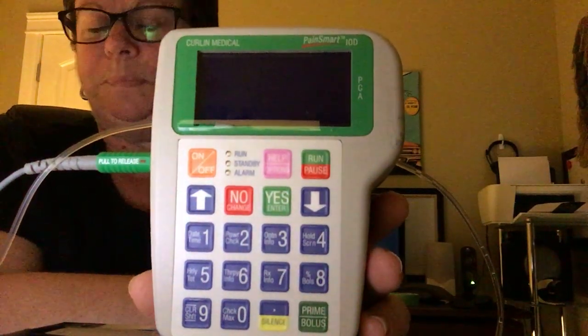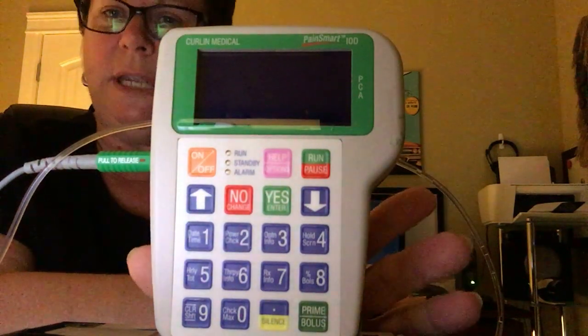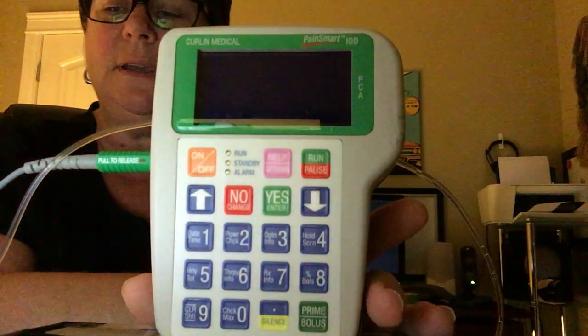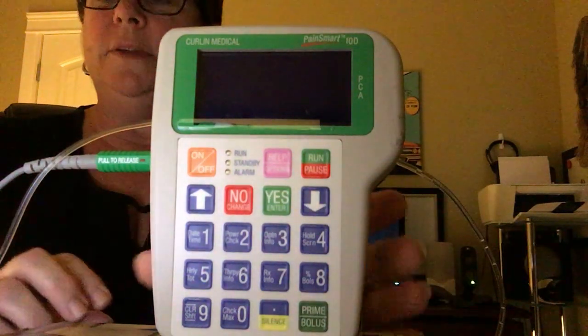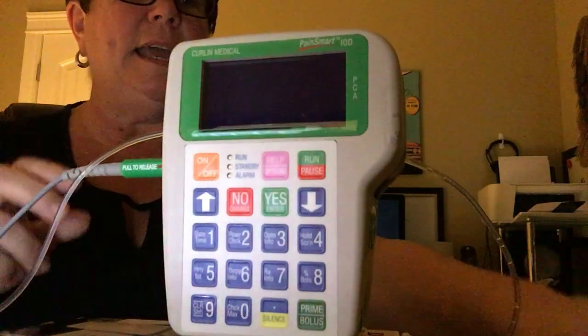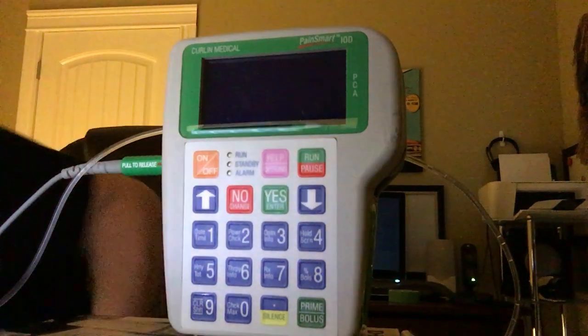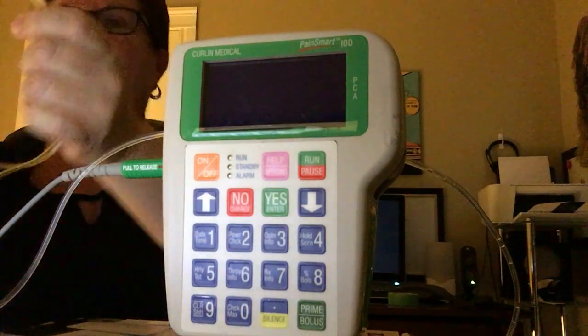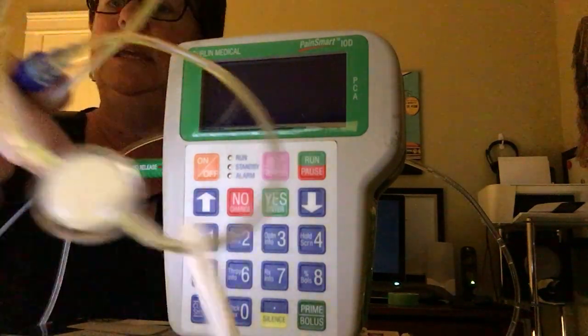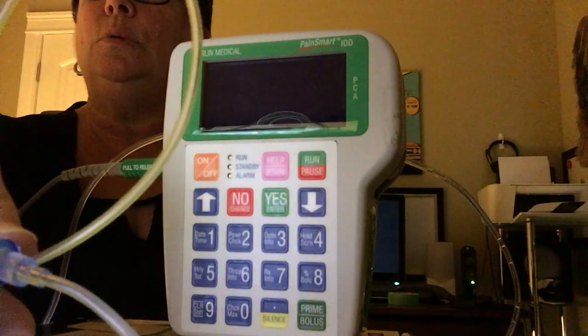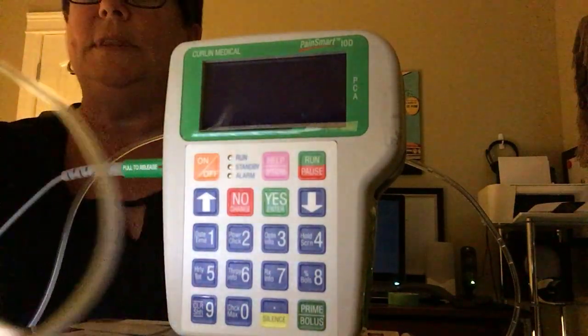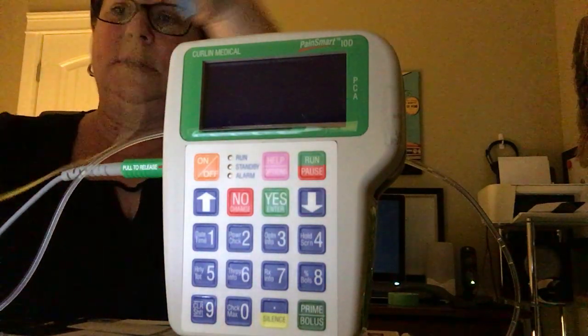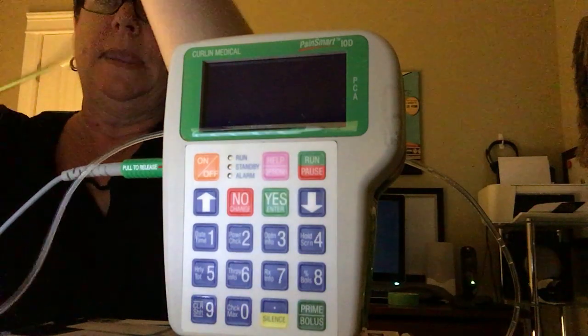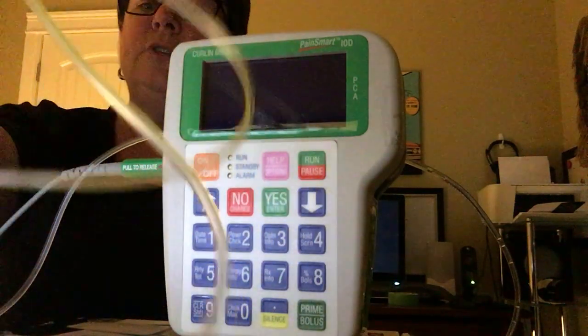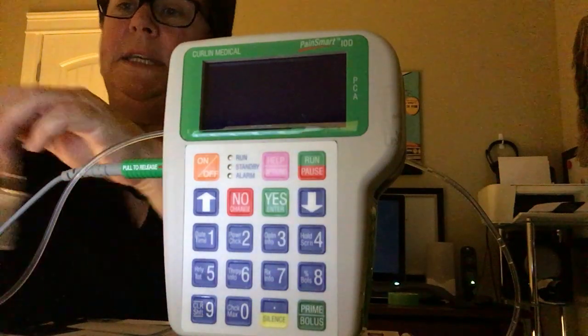So to look at the pump and to prime the tubing is unique to the pump. No other tubing can be used. And there's two sets of tubing, one for the PCA and one for the CLAI. So the CLAI, I don't know how well it transmits here, but you can see that it has a yellow line on it. The yellow will correlate with the screen. The nice thing about this CLAI tubing is when you look at it, there are 0 injection ports on it, meaning we should never be injecting into that.